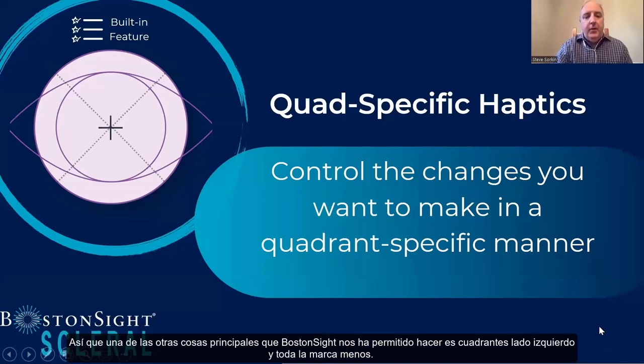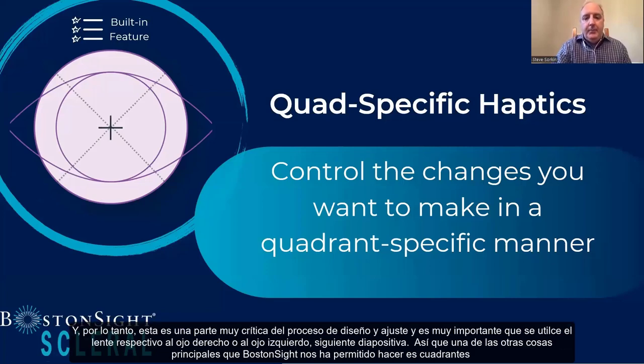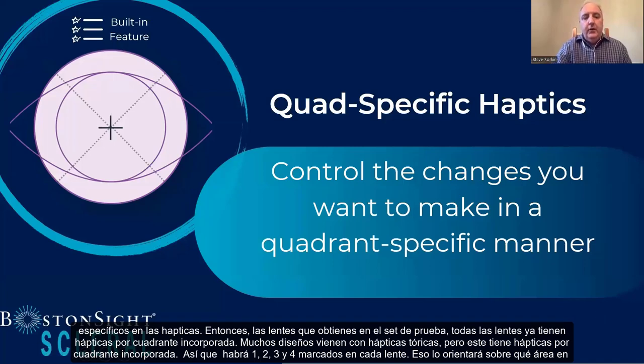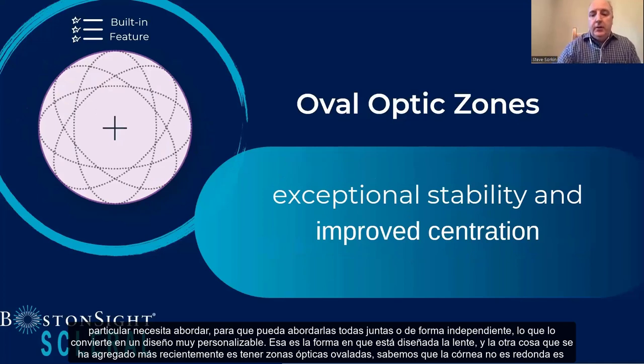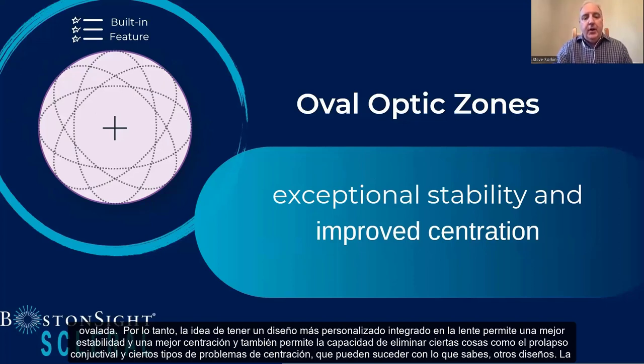Another key feature Boston Sight has built in is quad-specific haptics. All lenses in the fitting set already have built-in quadrant haptics — not just toric haptics, but true quad haptics. There will be numbers 1, 2, 3, and 4 marked on every lens, orienting you on which particular area to address. You can address all quadrants together or independently, making it a very customizable design. Additionally, oval optic zones have been added — since corneas are not round but oval, this more customized design built into the lens allows for better stability, improved centration, and eliminates issues like conjunctival prolapse and certain centration problems.